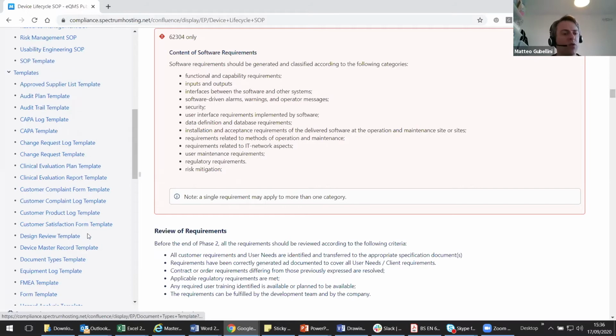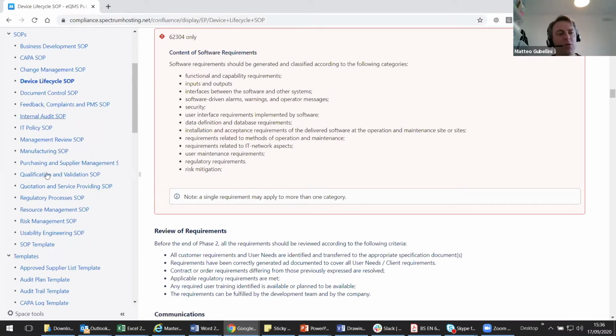Oh, actually, sorry, I forgot to mention, a recent addition to the quality system is a procedure for cybersecurity. So here we're not talking about, I don't know if you're familiar with, 27001. This is not data security or IT system security. Here we're talking about product security. There are regulatory guidance documents from the FDA that define a lot of requirements related to cybersecurity. There are especially two: one is about pre-market, and the other one is post-market.